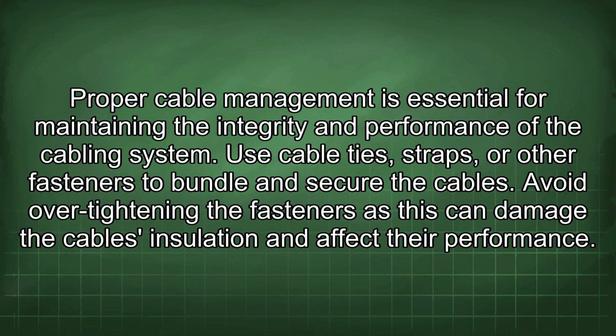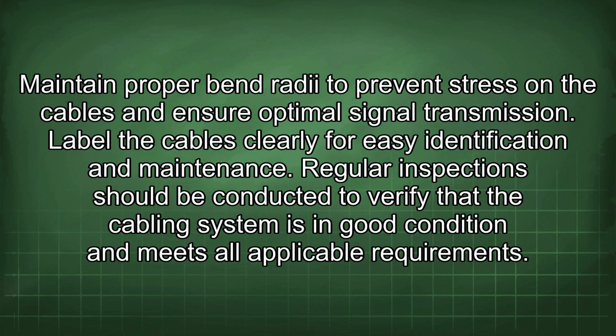Proper cable management is essential for maintaining the integrity and performance of the cabling system. Use cable ties, straps, or other fasteners to bundle and secure the cables. Avoid over-tightening the fasteners, as this can damage the cable's insulation and affect their performance. Maintain proper bend radii to prevent stress on the cables and ensure optimal signal transmission. Label the cables clearly for easy identification and maintenance.